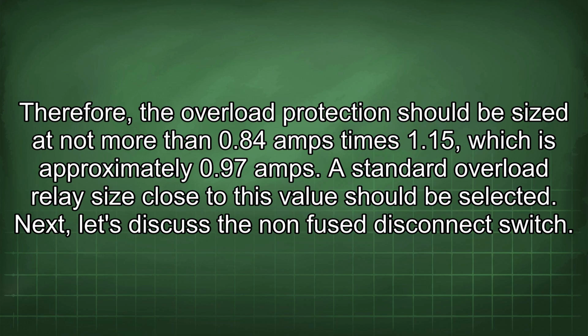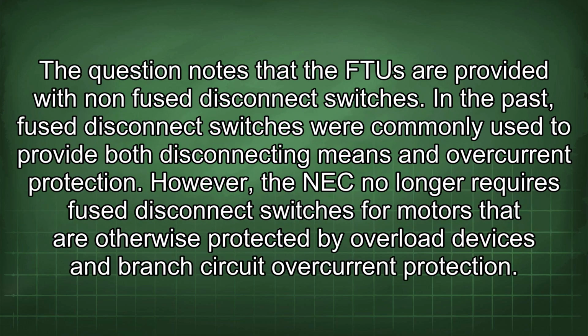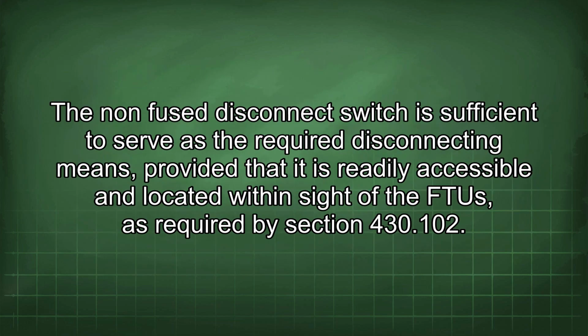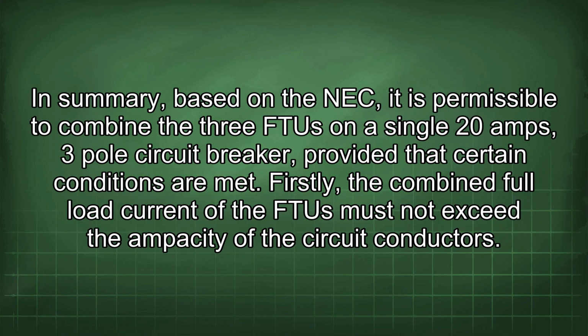Next, let's discuss the non-fused disconnect switch. The question notes that the FTUs are provided with non-fused disconnect switches. In the past, fused disconnect switches were commonly used to provide both disconnecting means and overcurrent protection. However, the NEC no longer requires fused disconnect switches for motors that are otherwise protected by overload devices and branch circuit overcurrent protection. The non-fused disconnect switch is sufficient to serve as the required disconnecting means, provided that it is readily accessible and located within sight of the FTU, as required by Section 430.102.